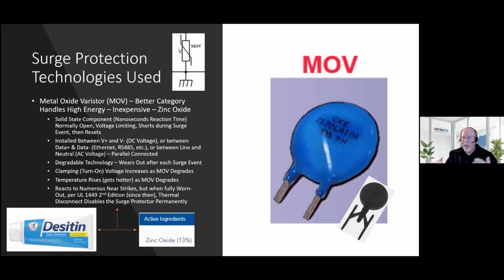And at some point it will catch fire. So Underwriters Laboratories, and we'll talk about this later too, established a requirement for surge protectors that they have thermal disconnects built into them. Especially for MOV technology, when it reaches a certain temperature at the end of its life, that thermal disconnect permanently disables the surge arrestor and keeps it from catching on fire.